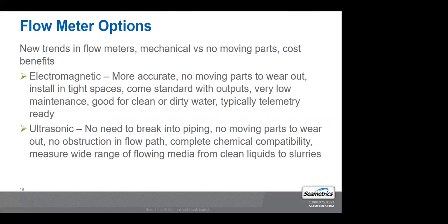When you look at overall cost of ownership on that meter, mag meters do not have moving parts to wear out. So at about the 4.5-year range, you would get a low battery indicator light that would come on. You go, oh, I need to replace the battery pack in this pretty soon. There are occasions where there's a lot of sediment, mineral buildup in the water, and there could be times when that meter would have to be removed from line and you take a cloth and clean the little electrodes off and put it back in line. But that's it. Mag meters are going to remain accurate versus mechanical moving parts meters, they wear out.